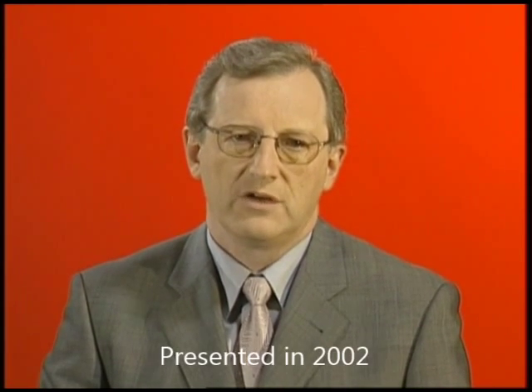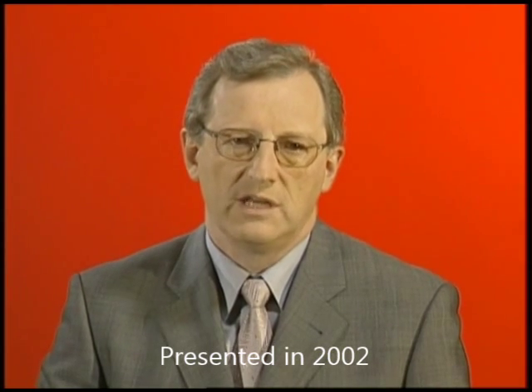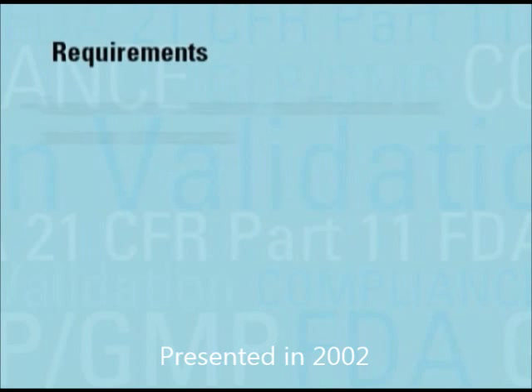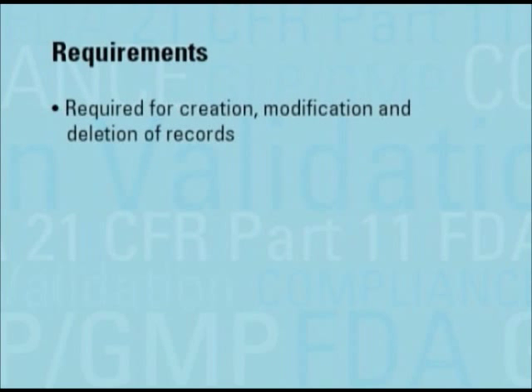For those of you who work in regulated environments, the audit trail itself is nothing new. What is new is a requirement that the computer must electronically record the audit trail, and the audit trail must be independent from the operator. Audit trails are required whenever records are created, modified, and deleted.